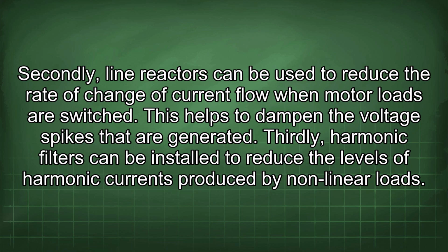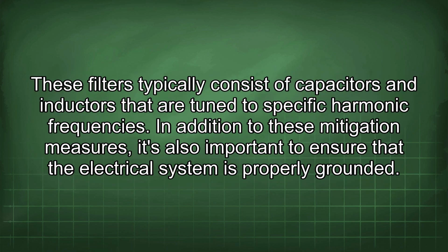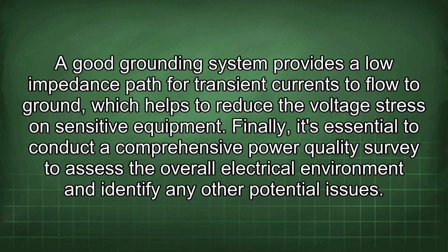Thirdly, harmonic filters can be installed to reduce the levels of harmonic currents produced by nonlinear loads. These filters typically consist of capacitors and inductors that are tuned to specific harmonic frequencies. In addition to these mitigation measures, it's also important to ensure that the electrical system is properly grounded. A good grounding system provides a low impedance path for transient currents to flow to ground, which helps to reduce the voltage stress on sensitive equipment.